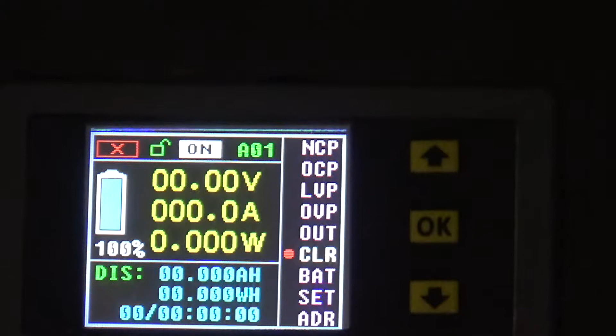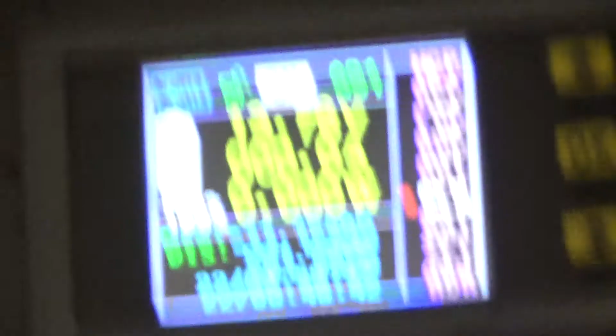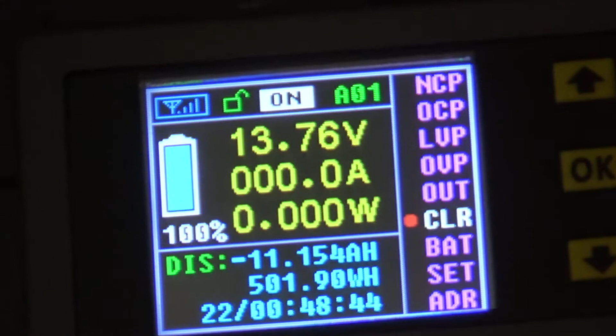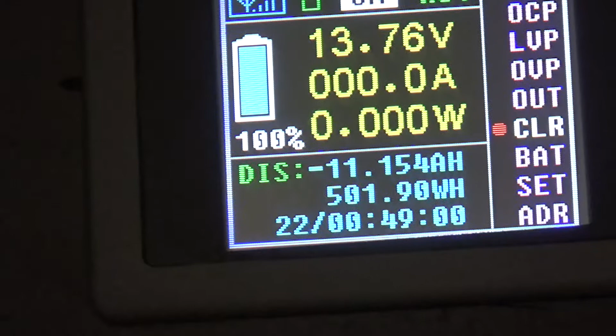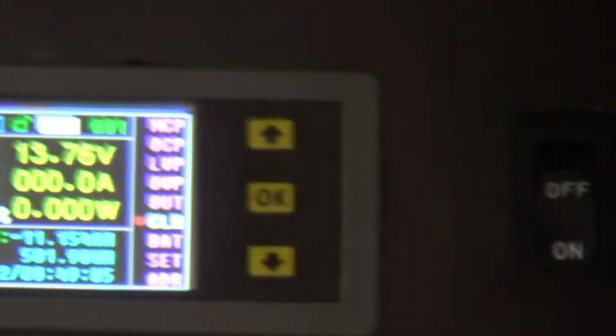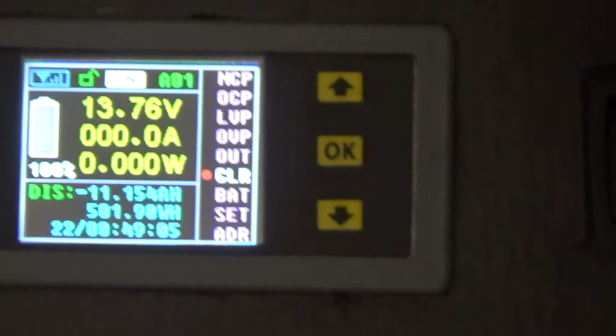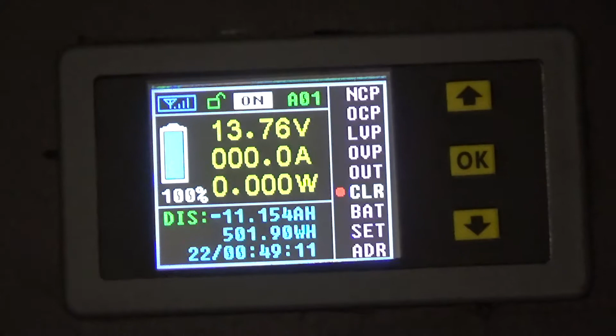I might have to move it to be closer or run a cable to it. But there it goes, you'll see it's connecting, disconnecting. So you see I'm at 13.76, that's my float, right? So it says it's discharging 11 amps, but that's not a discharge - that's just, because I don't have my solar panels hooked up, that's the extra excess that the solar panels are creating that it's not measuring. So it's complicated, but I put that thing in.